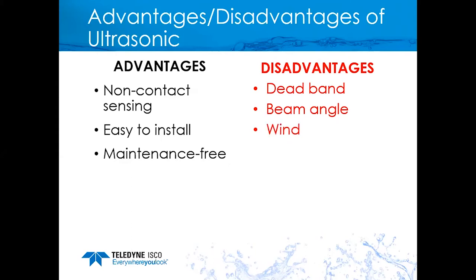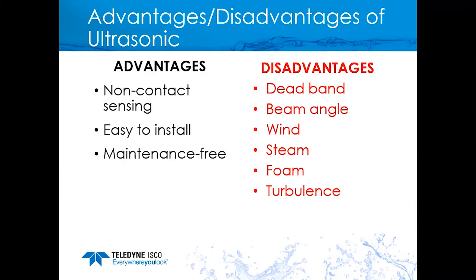Wind can also be a factor because we're transmitting a sound wave that can be blown away, reducing signal strength. Steam can be an issue as it bounces off micro water particles in the air, potentially reflecting in the deadband or giving a false signal. Foam can absorb the ultrasonic signal so it may not reach the surface — if you have foaming in your channel, an ultrasonic would not be a good option. Turbulence is also an issue since ultrasonics need a flat, smooth surface for a return echo; turbulence disperses the sound wave, giving reduced or no signal.